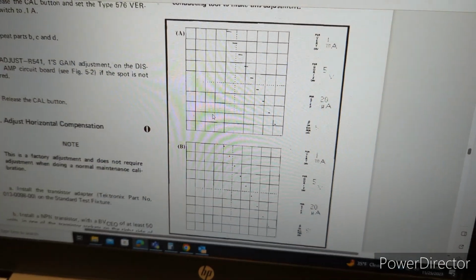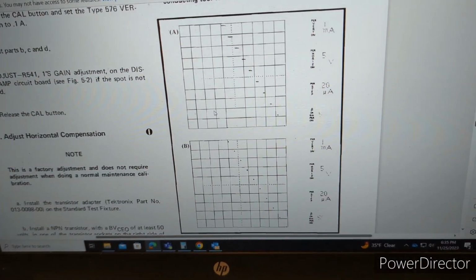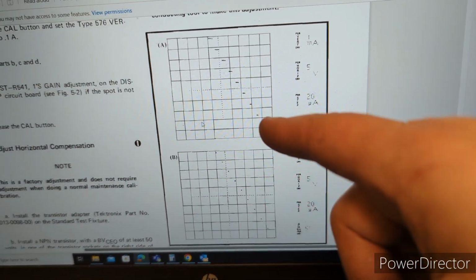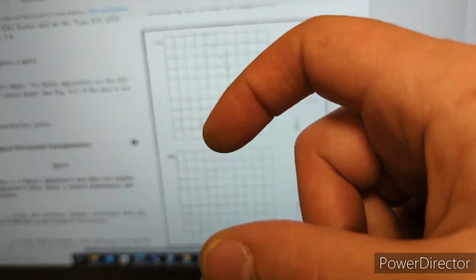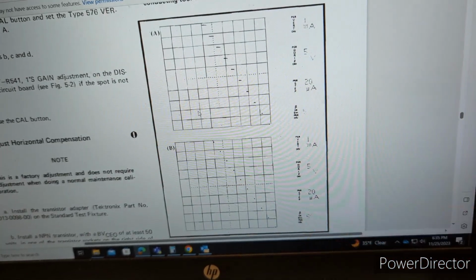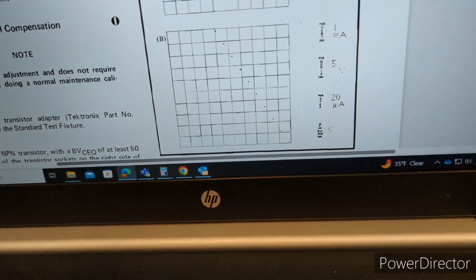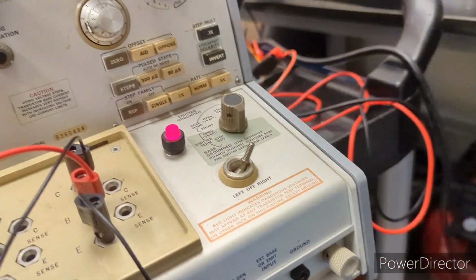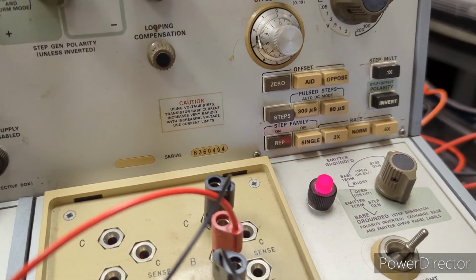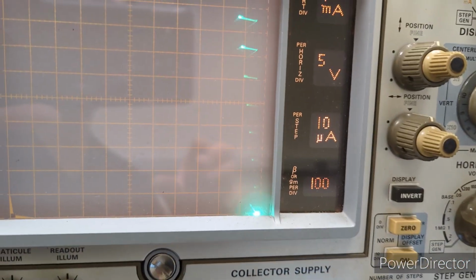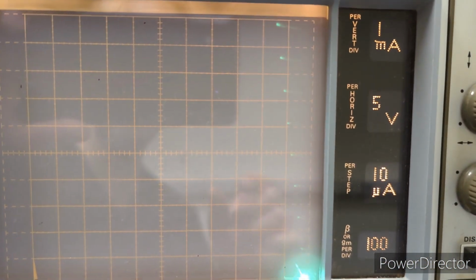So this looks very similar to the example given in the service manual. Now, it looks like what we have is a bit closer to the first one. You can see each step, the traces look a little bit elongated, whereas they should be more of a fine point for each step. We're in the pulse step mode, so that automatically puts it in DC mode, so we really should only be seeing a fine point and not these long traces. I guess that's what they're getting at here.